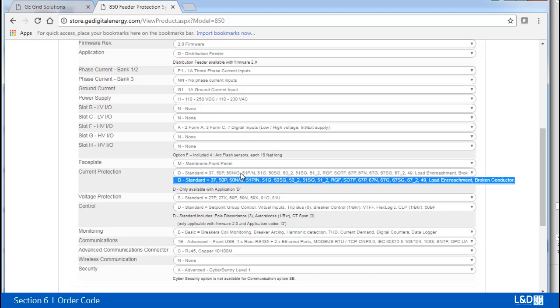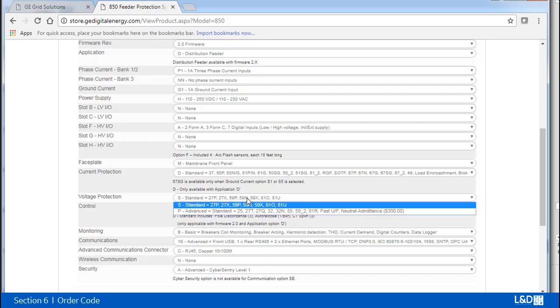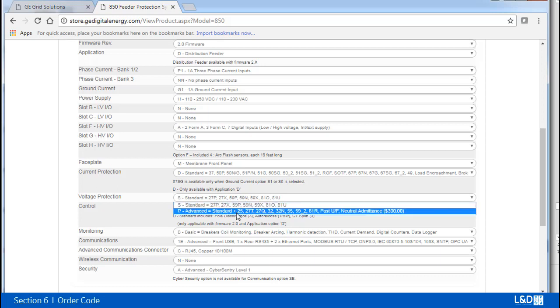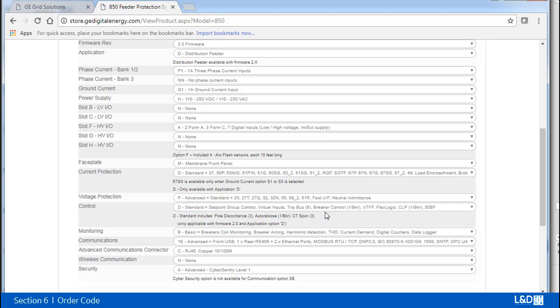For the current protection, I can choose the standard, because the note says this is only available with application D. And for the voltage, I can choose standard or advanced, and you will see the difference is the standard plus a lot of other functions. It also has a note. Standard includes pole discordance, auto reclose, CT supervision. So this is the good side of using the online tools. It applies all these conditions automatically when you define a valid order code.